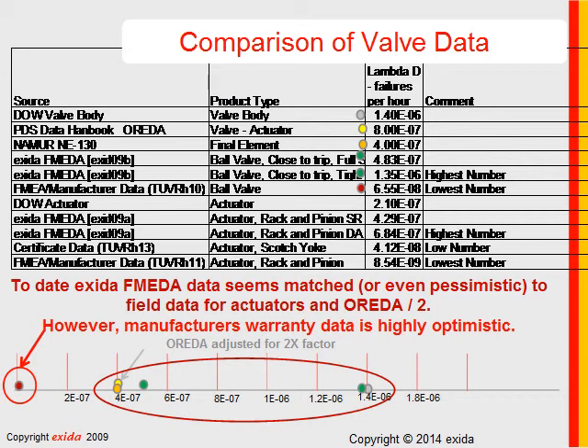A question came in: are operating conditions considered in FMEDA results? Yes, to a certain extent. We have seven different operational profiles which list a whole series of environmental variables based on international standards. The FMEDA component data is published as a function of the operational variable, so for any given part we would have seven different failure rates accounting for seven different operational profiles.